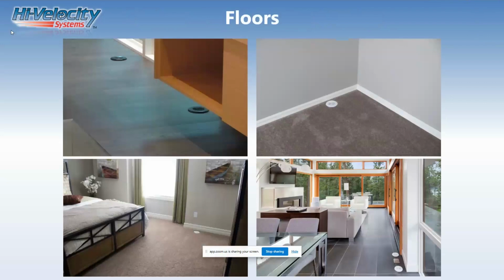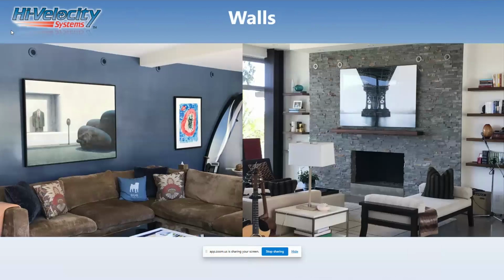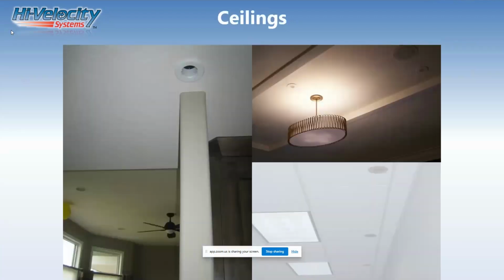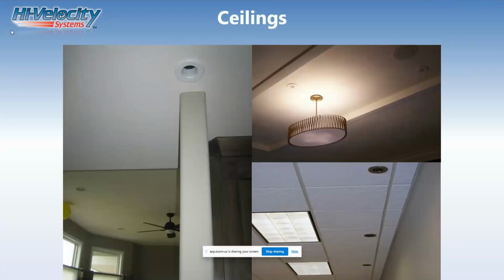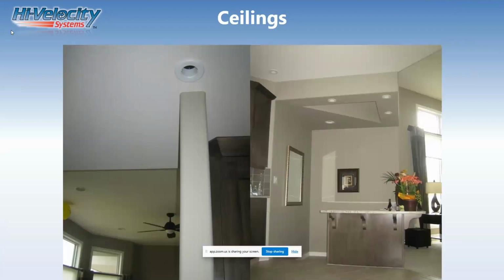Floor applications. Again, we're going 6 inches off the wall, whether it's the floor or the ceiling, never in the middle of the room. And we don't have to be in front of the heat loss or heat gain locations, typically windows. I need to just get in that room, and that's how well I move the air. Wall applications, also beautiful. High wall applications, I can move that air. It's not disturbing anybody. So all kinds of applications like that. Ceiling, another one. It looks like a pot light. There's no need for the grill in it. I can take the grill out and it looks exactly like a pot light.